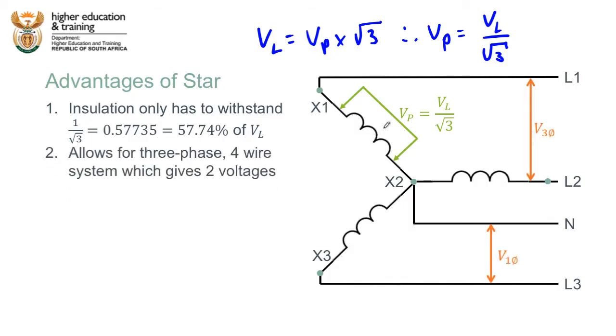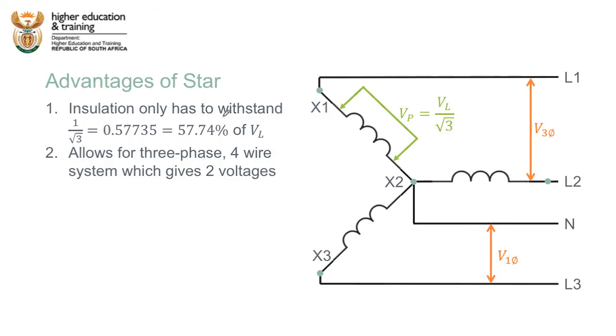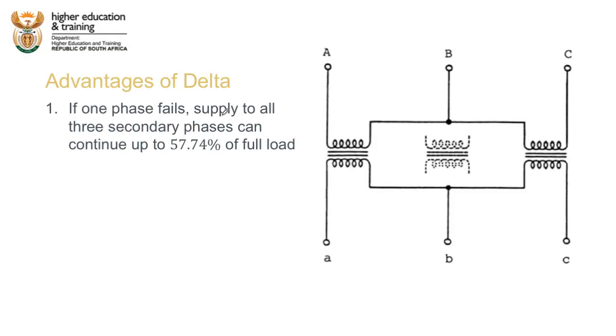Secondly, a star configuration gives us the potential for a four-wire system where we can get two distinct voltages: either the full three-phase voltage between any two lines, or a single-phase voltage between any line and the neutral point. The advantage of delta is that if one of the phases fails, supply to all three secondary phases can continue, but only to about 57.74% of the full load. Now let's look at an example.